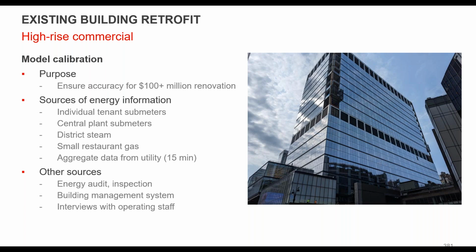And then other things, we did a fairly extensive audit, lots of inspections on this building. There is a BMS, it's being upgraded now, but it was working. And then in this case, the operating staff was the biggest source of information, right? The guy that runs this building, he's been in the building for 25 years. So he knew everything, he knew how everything ran. And that really provided a lot of key insights into setting the controls correctly and things like that.